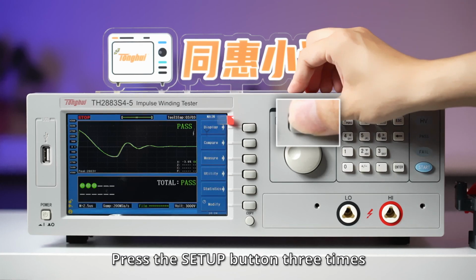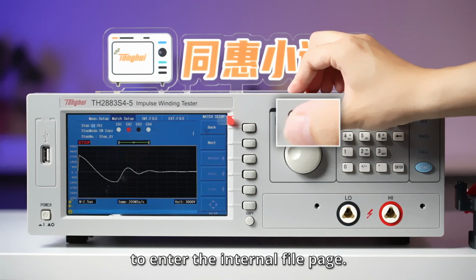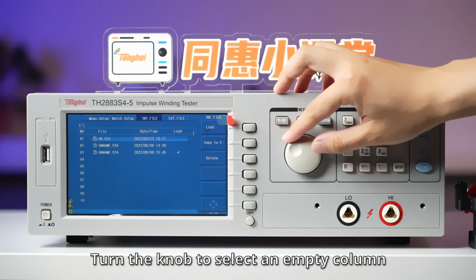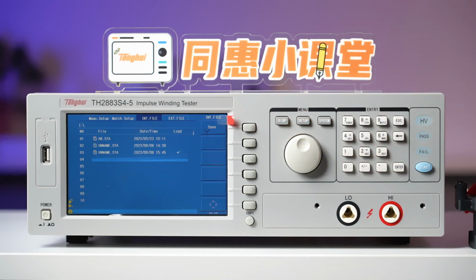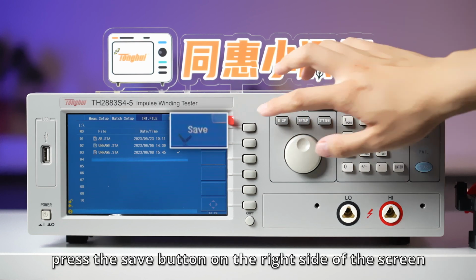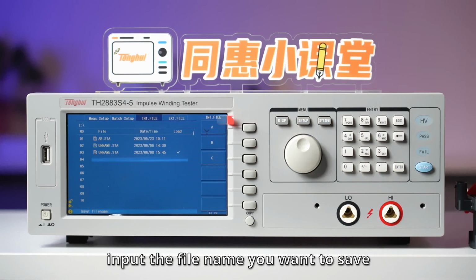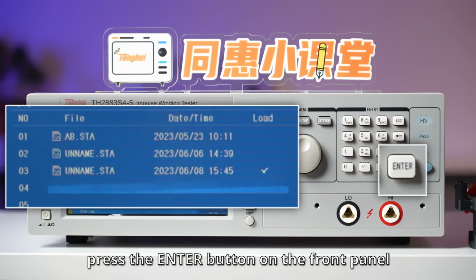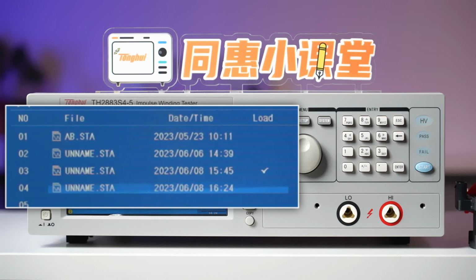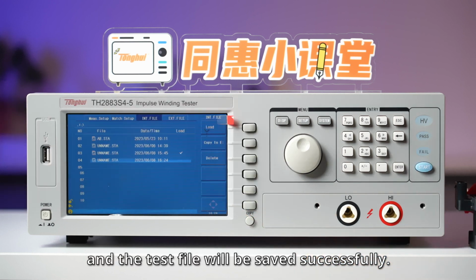Save and load the test files. Press Setup button 3 times to enter the internal file page. Turn the knob to select an empty column. Press the Save button on the right side of the screen. Input the file name you want to save. Press the Enter button on the front panel, and the test file will be saved successfully.